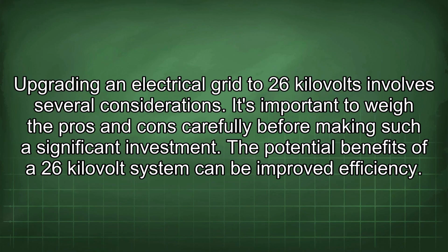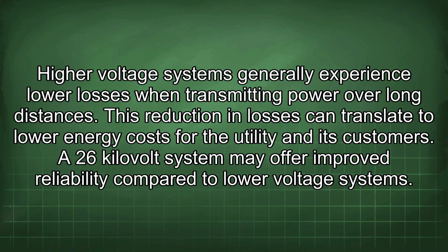Upgrading an electrical grid to 26 kilovolts involves several considerations. It's important to weigh the pros and cons carefully before making such a significant investment. The potential benefits of a 26 kilovolt system can be improved efficiency. Higher voltage systems generally experience lower losses when transmitting power over long distances. This reduction in losses can translate to lower energy costs for the utility and its customers.